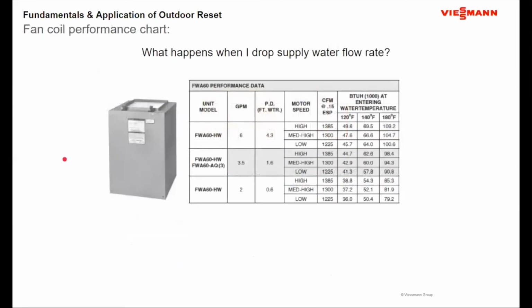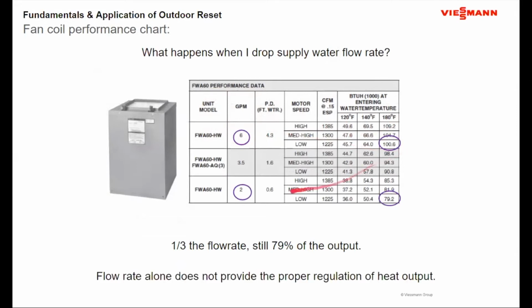Same thing happens with air handling units. So if I look here at 6 gallons per minute, from 180, I get 100,000 BTUs from that heat emitter. If I drop it down to 2 gallons per minute, I've dropped the flow rate to a third of the original flow rate. But if you look at the numbers here, I'm still getting about 79% of the output.